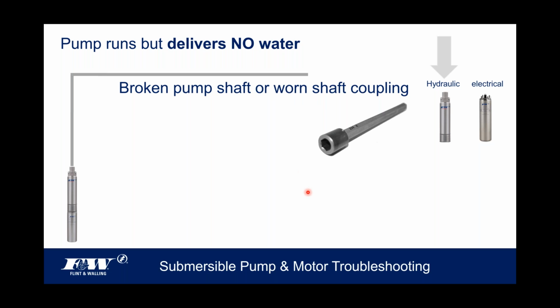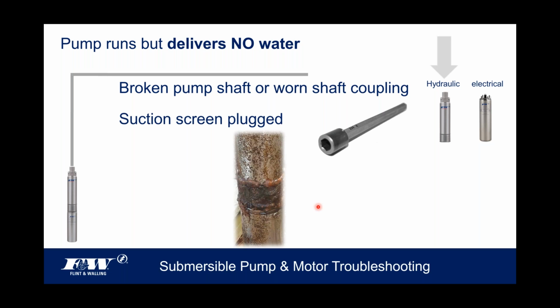And again, with so many of these pumps that are non-repairable, some of these things that I'm talking about, the only way you would be able to determine it is to take the pump and motor apart and pull down on that coupling and see if that shaft comes right out of the assembly. If it's broken, more than likely it will. Again, going back to that suction screen, if it gets clogged completely, which almost looks like the one on the screen is, that pump can sit there running and it's not going to deliver water because it can't receive any through that completely clogged suction screen.